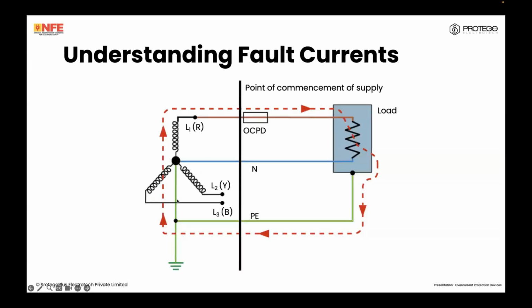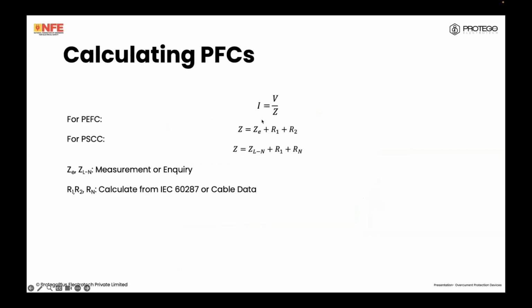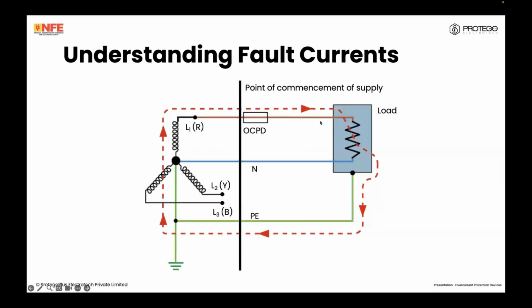Now, how are fault currents created? If this is our transformer, you've got a star here, RYB. Consider this single phase. This is our point of commencement of supply. We've got our overcurrent protection device, our neutral and our protective earth. When a fault occurs, either through line to neutral or line to protective earth, there is essentially a fault of negligible impedance, and the magnitude of this earth fault current depends on the resistance and impedance of these wires. The maximum fault current will occur if the fault occurs closest to the transformer, which is here. The minimum occurs if it is here. So to calculate, we need the loop impedance values for here for the maximum and here for the minimum.